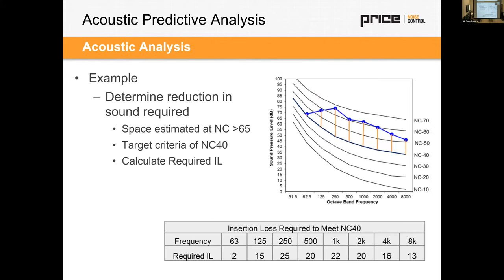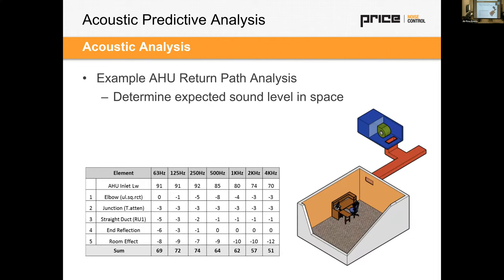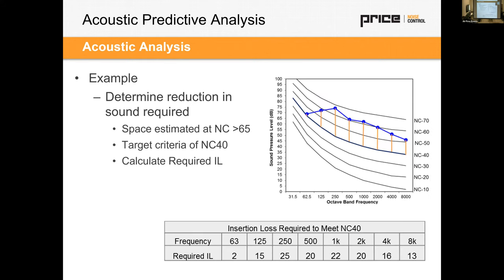What does that mean? Well, usually we take that and we graphically plot it on an NC curve. In this case, you would take those individual sound pressure levels and plot them on this NC chart to get a noise criteria value, or an NC value. The way that's done is the highest curve that's crossed on this NC chart, which looks like it would be around here, would set your NC value. In this case, we're actually around NC65, which is quite loud. If we wanted to get down to NC40, you have to reduce each of those octave bands down an appropriate level to get to that NC40 curve.